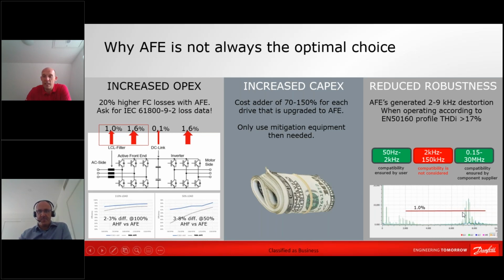And that means that the energy will now go from the filter that is injecting into the vulnerable part, and the vulnerable part will react by sucking up the energy and requesting more, and the filter will just start exciting the harmonics. And at the end of the day, if it's an EMC filter in the drive, the EMC filter will explode.